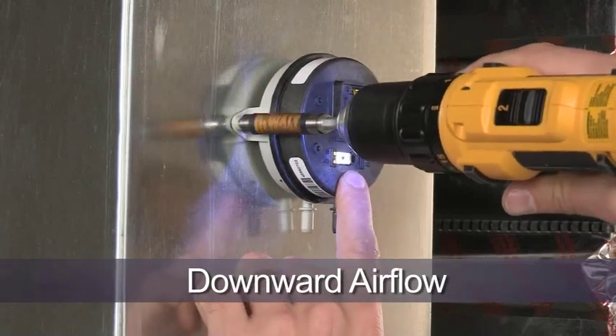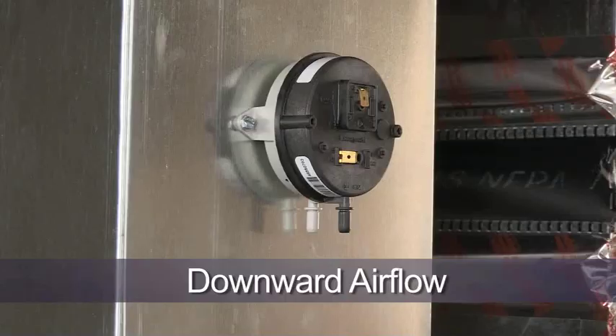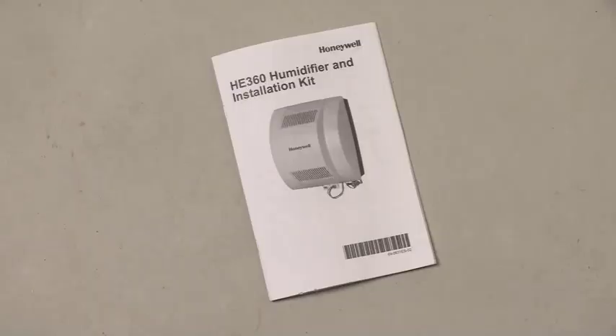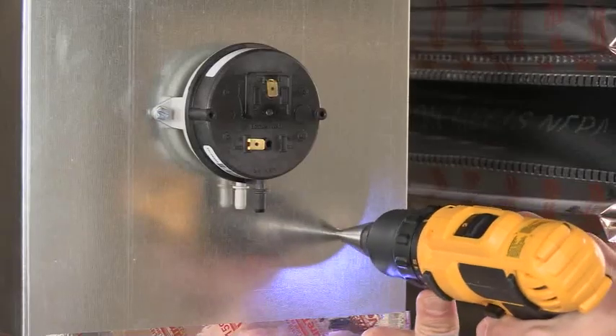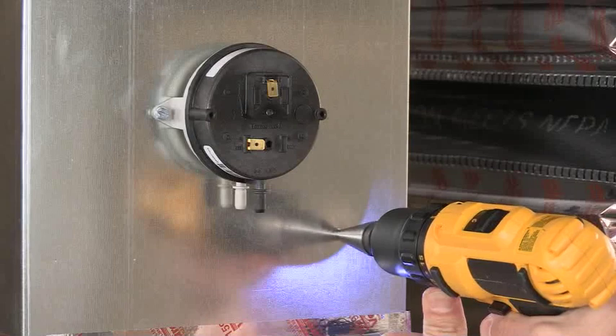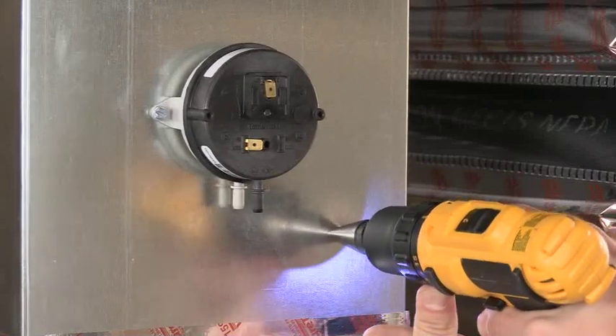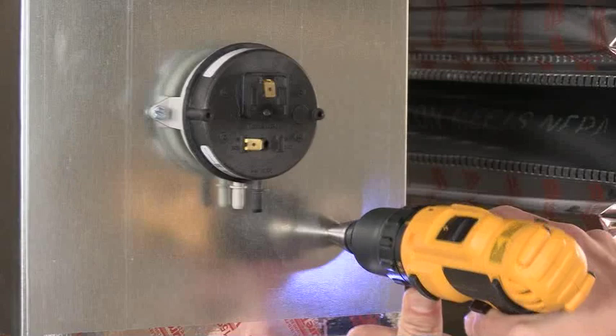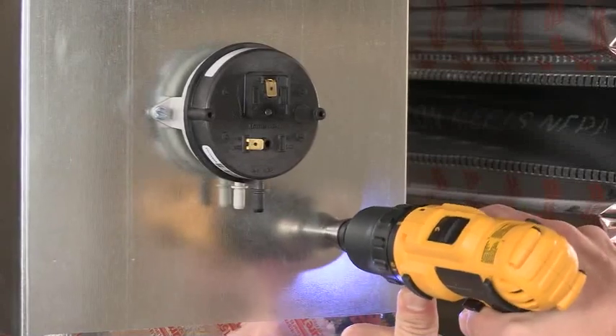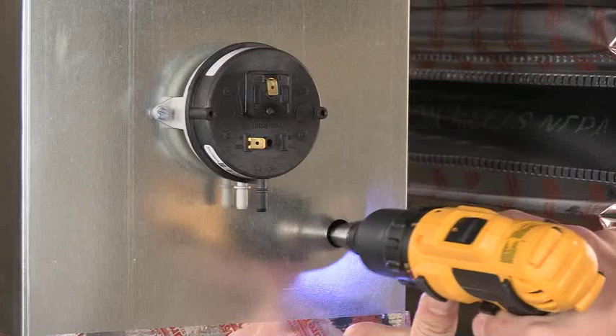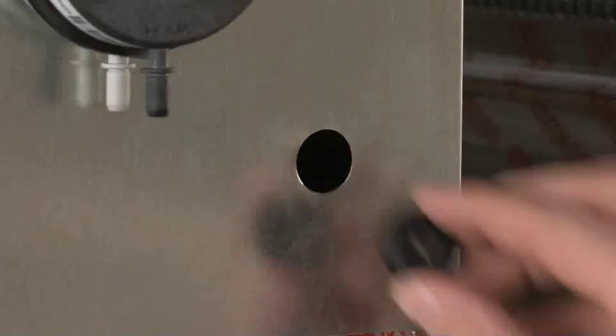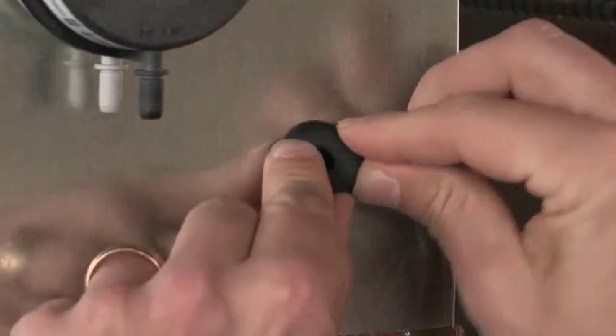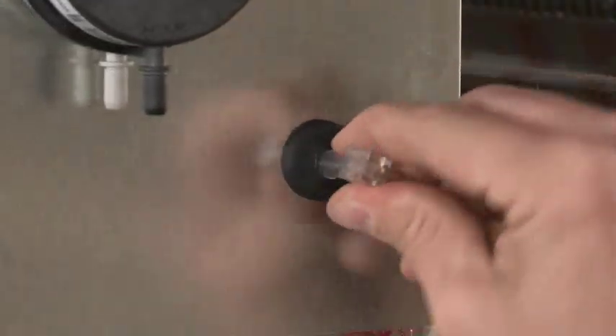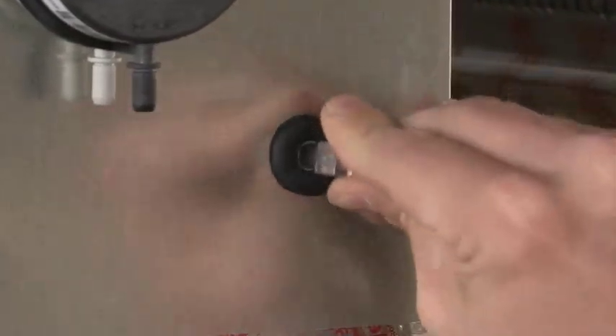The best method for detecting air movement is to tap into both the supply and return ductwork, as we will demonstrate here. Refer to the manual for alternative methods to fit your application. Drill a 3/4 inch diameter hole in the appropriate duct or ducts based upon where you installed the humidifier. Make sure the hole is within 10 feet of the switch so that the tubing can reach the pressure switch. Once the hole is cut, insert the rubber gasket. Then, insert the clear plastic elbow into the rubber gasket.